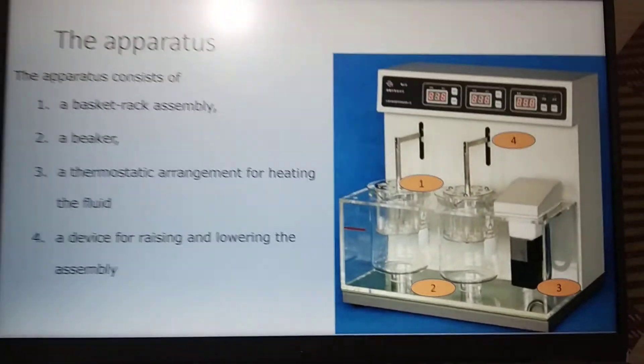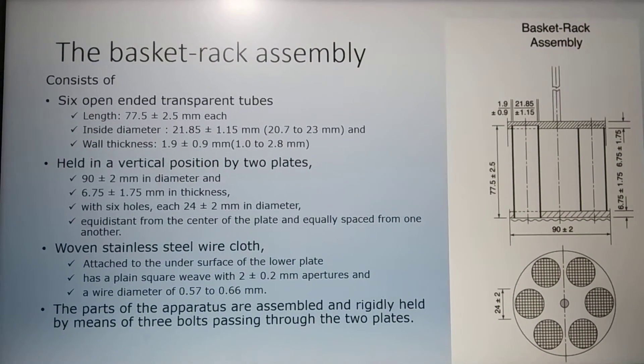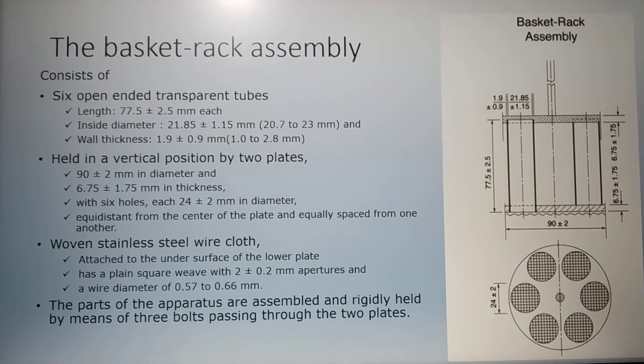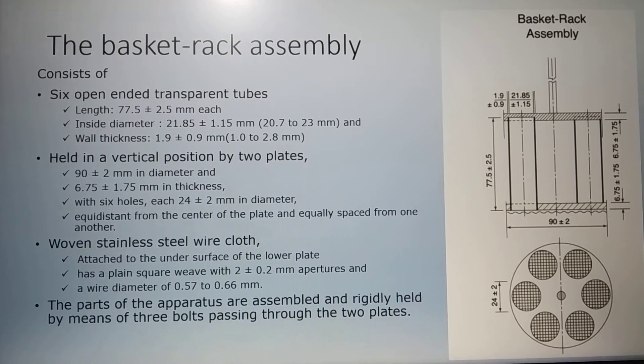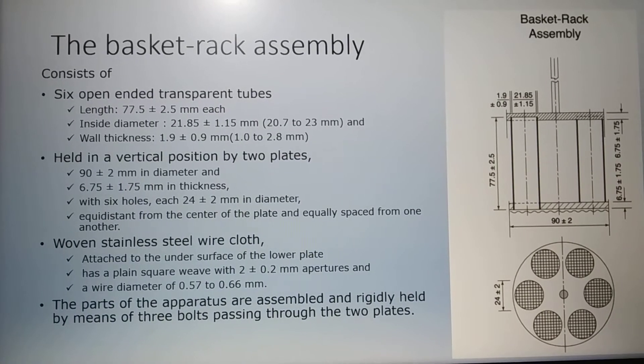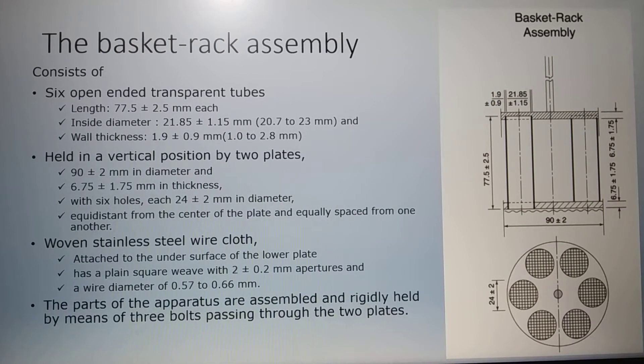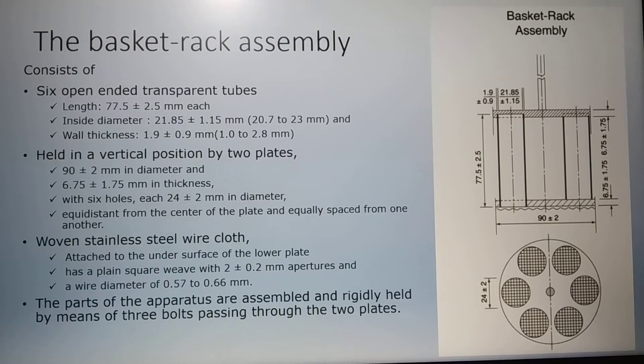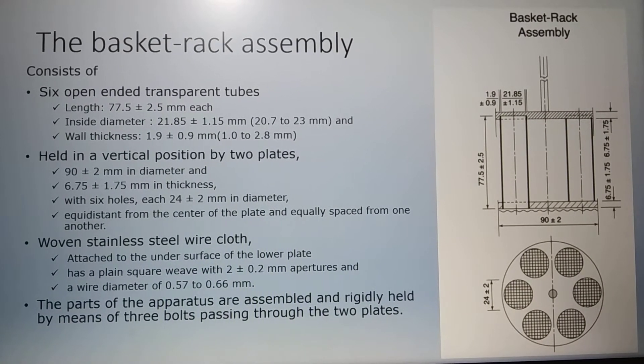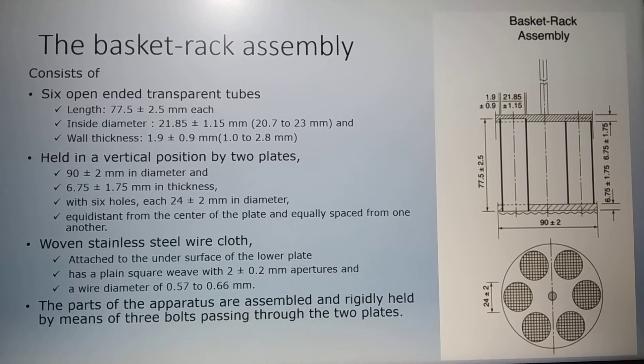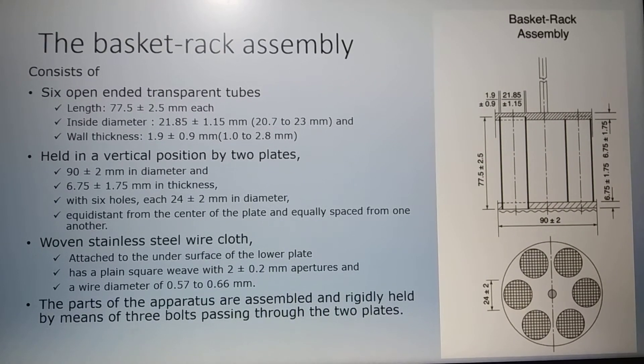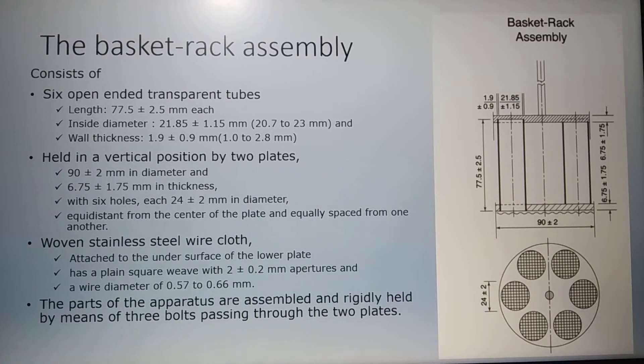We are now going to learn in depth about the basket rack assembly. This assembly consists of six open-ended transparent tubes. The dimensions of the tubes are defined in the USP. The tubes are of length 77.5 plus or minus 2 mm each. The inside diameter of the tubes is 21.85 plus or minus 1.15 mm.